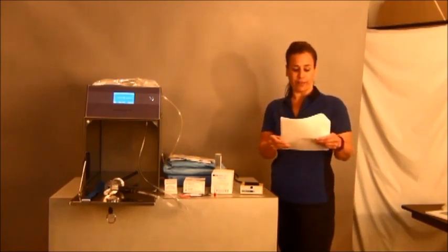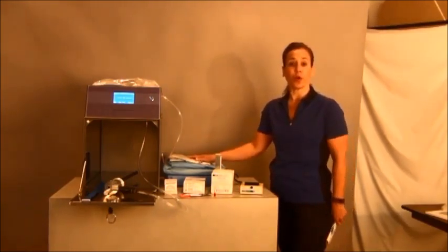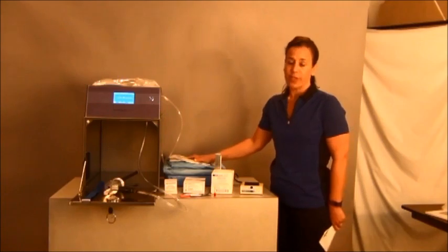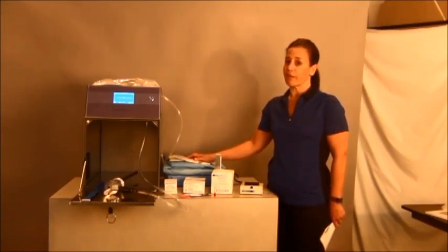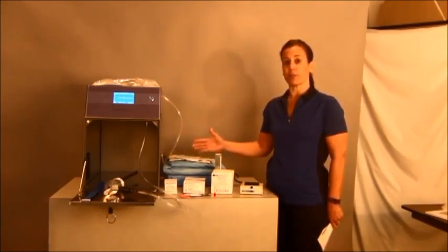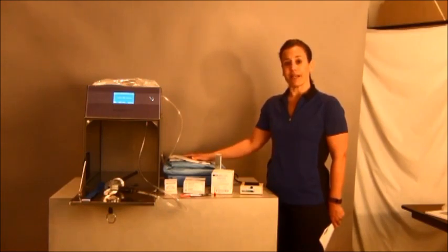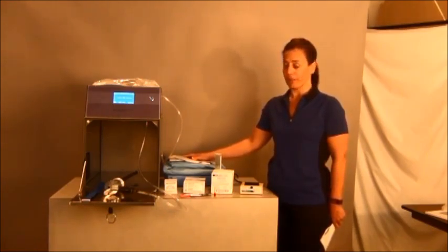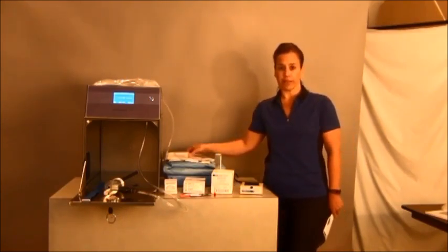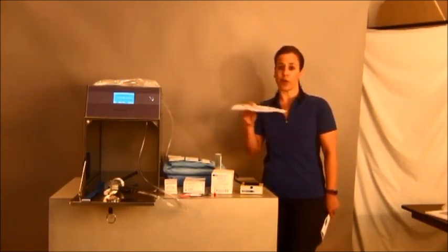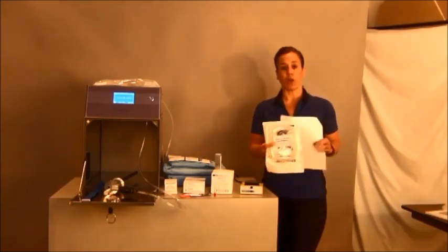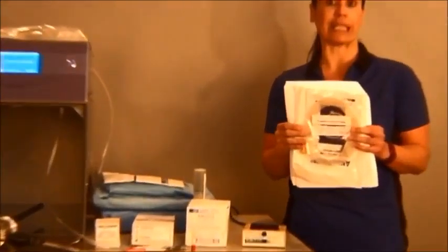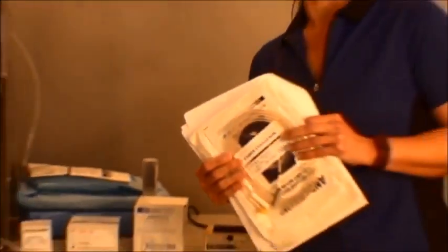When preparing your items, you want to go through 4 basic steps of cleaning. You want to disassemble every item to its lowest possible point. Ethylene oxide needs a clear path to penetrate throughout the entire item. You want to keep your items humid, and you can do so by washing these. You want to wash them till they are surgically clean. You want to dry the items, and this portion is also very important.